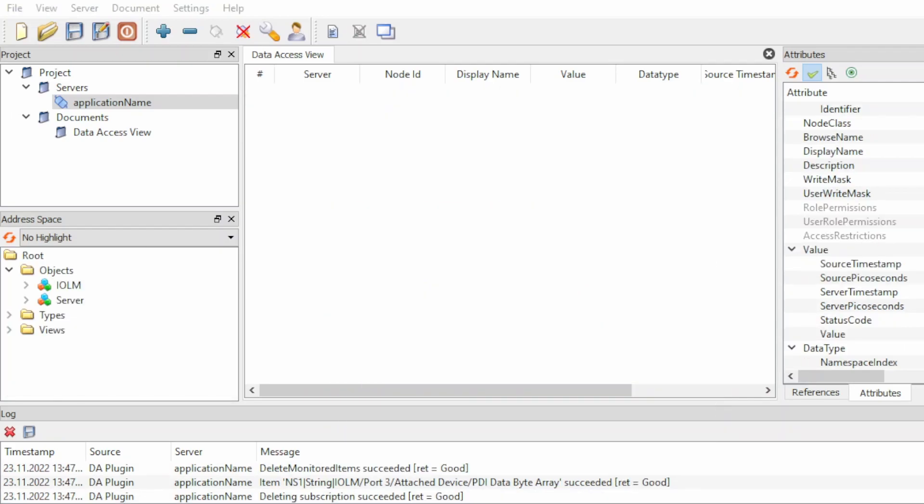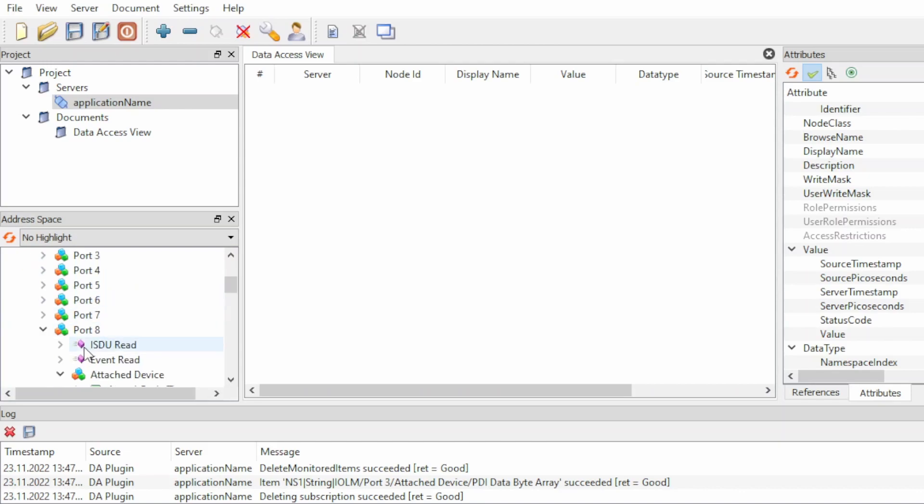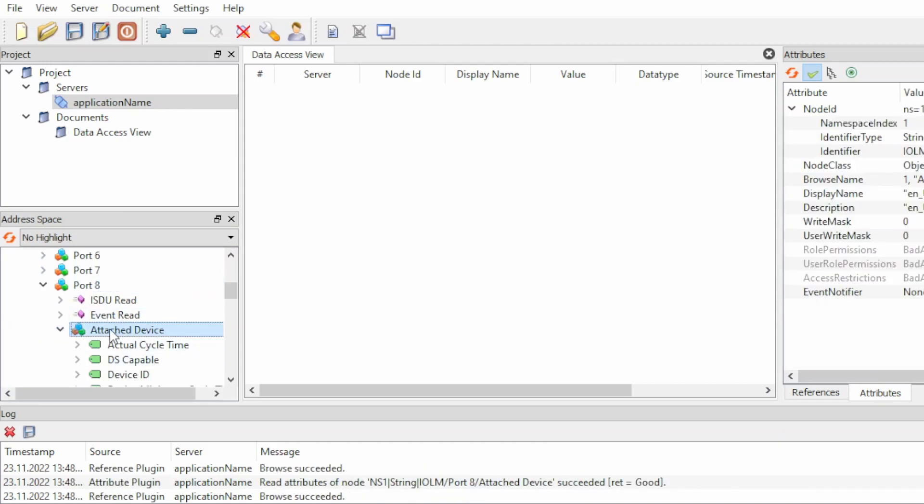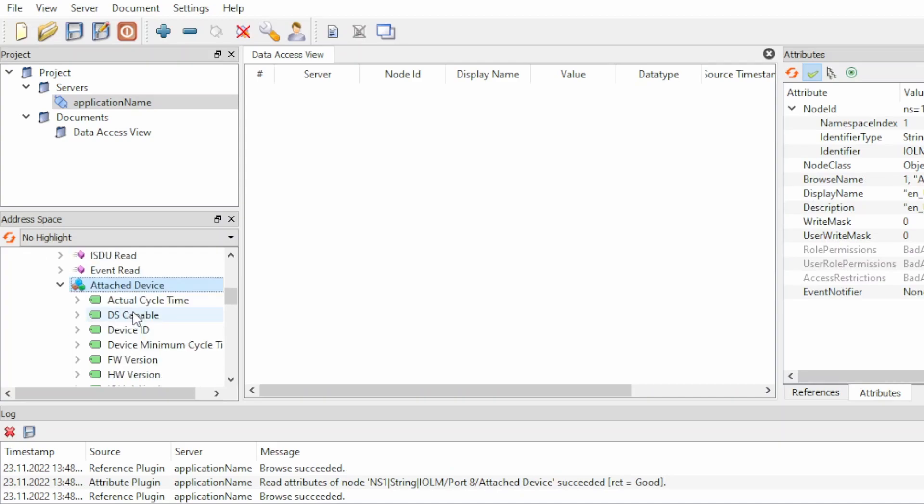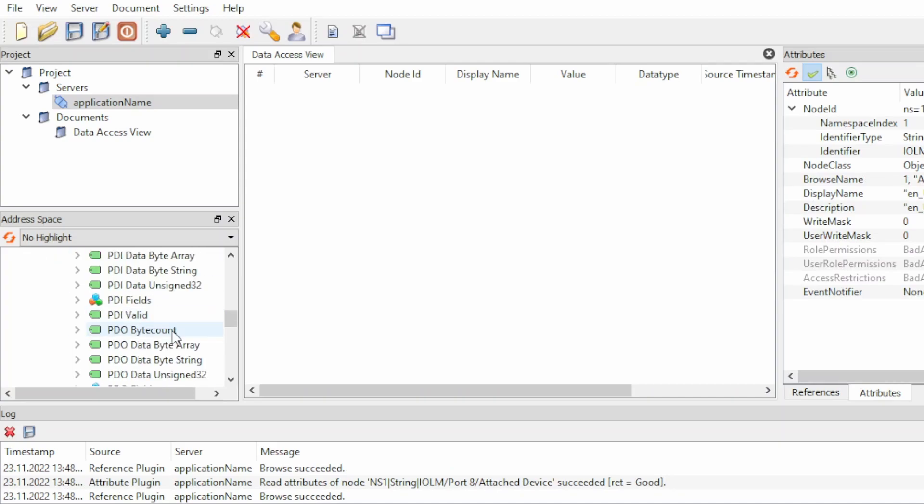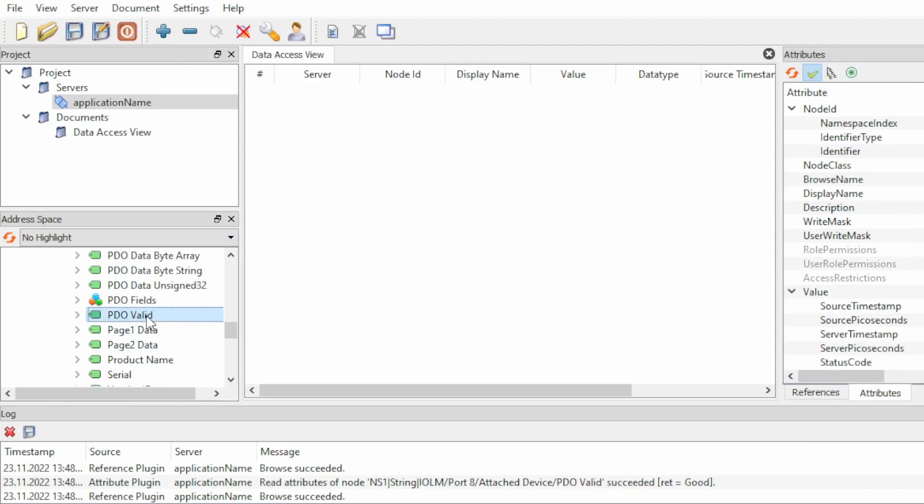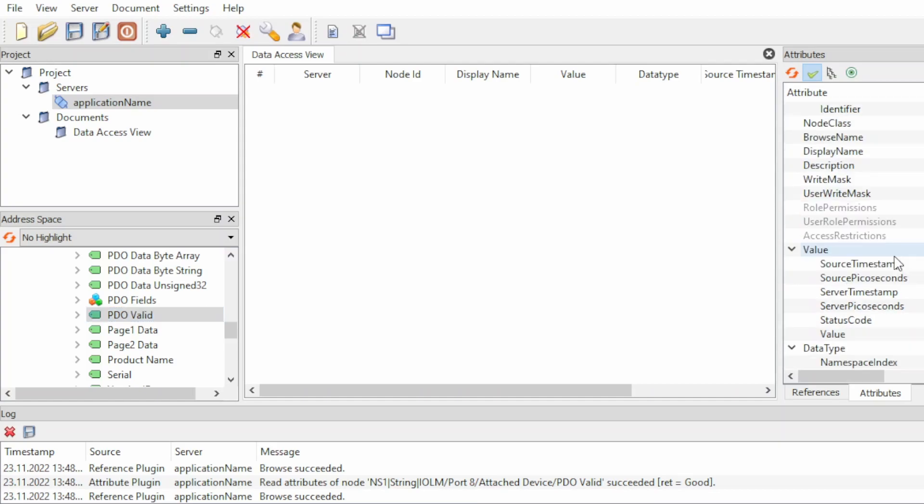We can also take a look at the other IO-Link device that is connected to port 8. We go into port 8 and attached device, and because we have both inputs and outputs connected to this, we need to change the PDO valid element. We have to set it to true, so that's done like this.